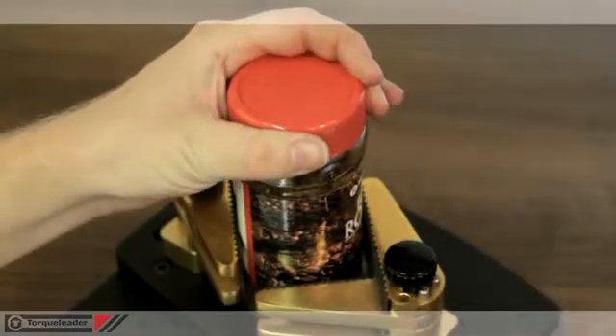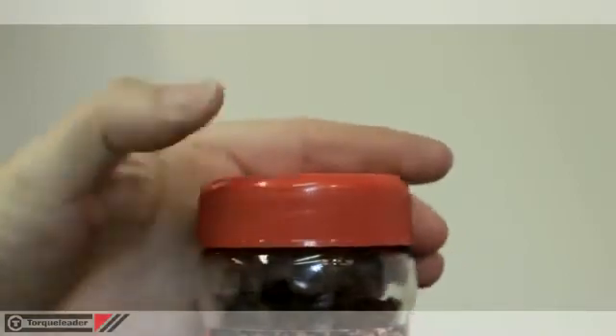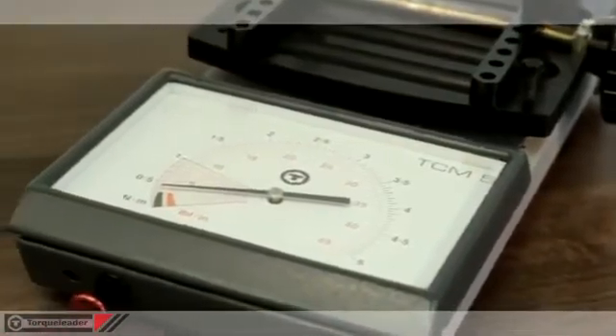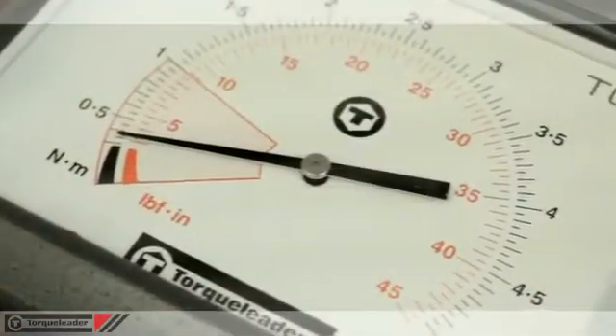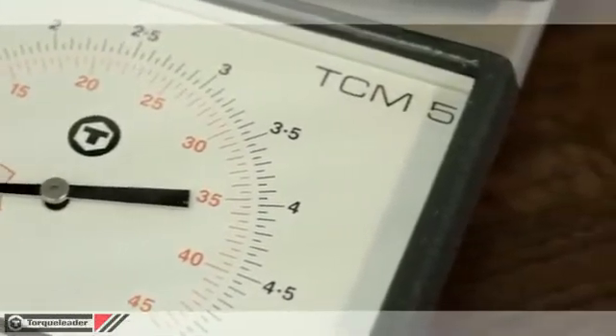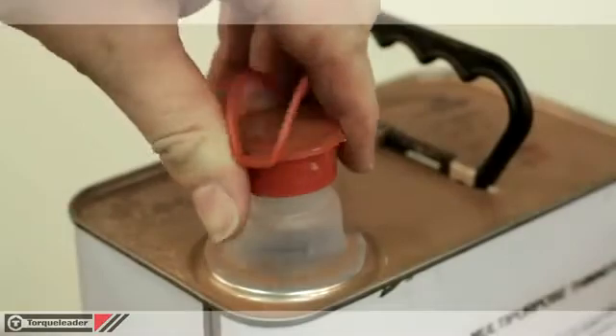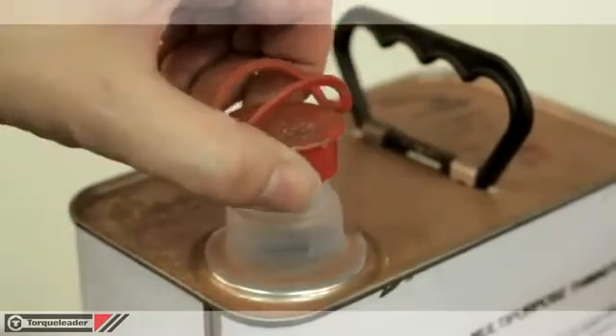This ensures that caps are correctly tightened and sealed but remain easy to open and reseal by the customer. The five models measure torque values up to 15 Newton meters or 132 pound force inches in both tightening and loosening directions.